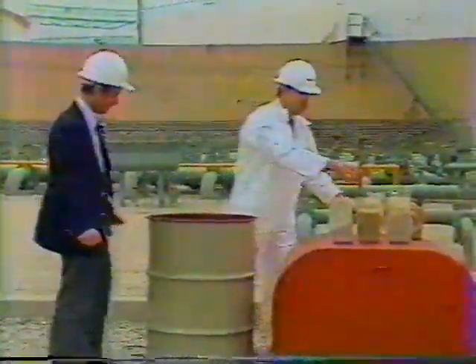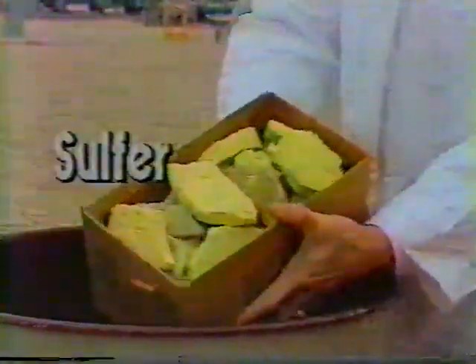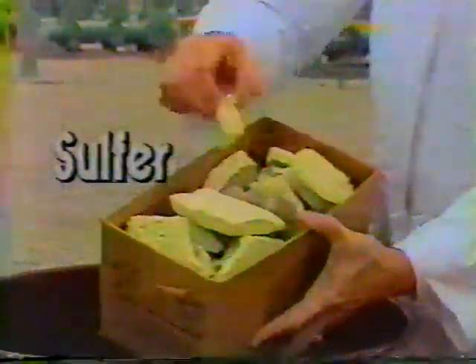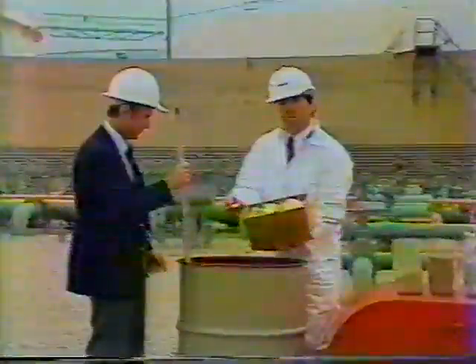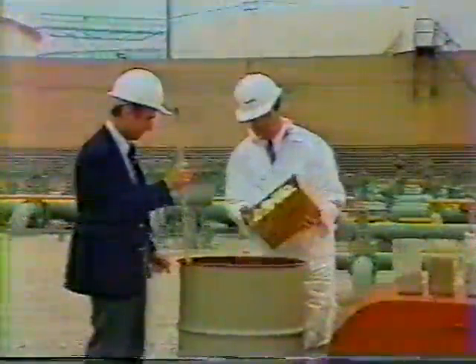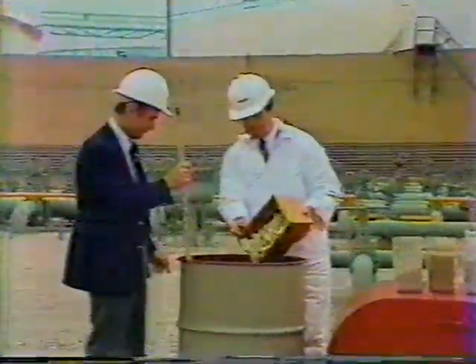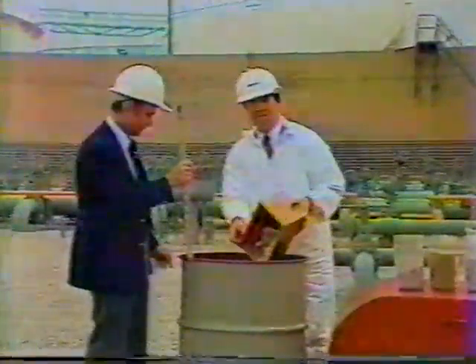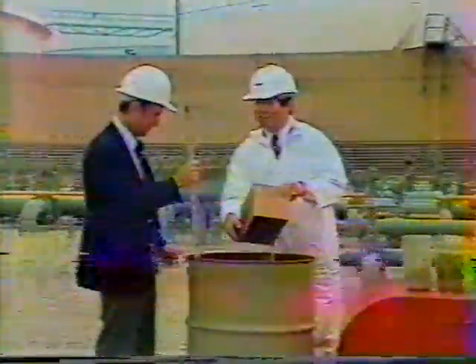Now, George, I'd like you to be the witch and do the stirring for me on this one here. Right. Now we have about 11 pounds of sulfur. Now, again, this is in a solid form. In the oil, this would be dissolved and be in solution. And we're going to throw this in there now, too. Now, this sulfur, although it's corrosive, can be neutralized through the proper use of an alkaline cylinder oil, such as you're using in your Sulzer engines, Mobilgard 570.